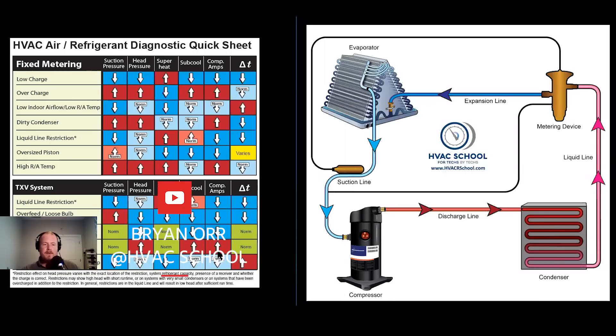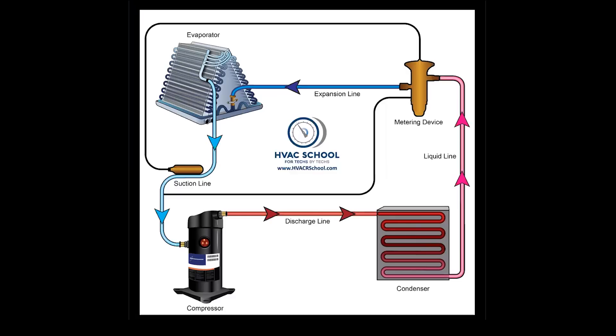Let's talk about one of the most common misdiagnoses that technicians get, or confusions they have about restrictions. A common thing that techs believe is that if you have a liquid line restriction — say a clogged liquid line filter dryer, a metering device that's under-metering meaning it's not allowing enough flow through it, or a service valve that's not open all the way — they think you're going to have higher head pressure.